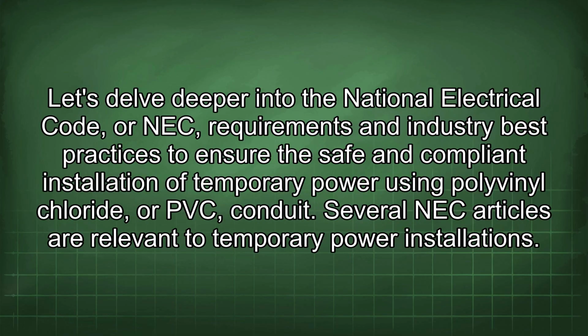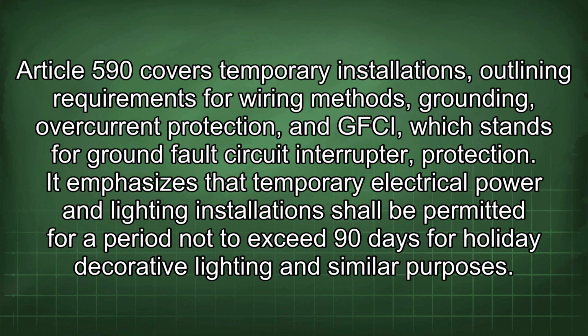Let's delve deeper into the National Electrical Code, or NEC, requirements and industry best practices to ensure the safe and compliant installation of temporary power using polyvinyl chloride, or PVC, conduit. Several NEC articles are relevant to temporary power installations. Article 590 covers temporary installations, outlining requirements for wiring methods, grounding, overcurrent protection, and GFCI, which stands for Ground Fault Circuit Interrupter protection. It emphasizes that temporary electrical power and lighting installation shall be permitted for a period not to exceed 90 days for holiday, decorative lighting, and similar purposes.